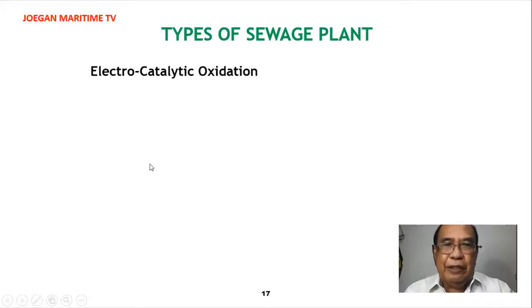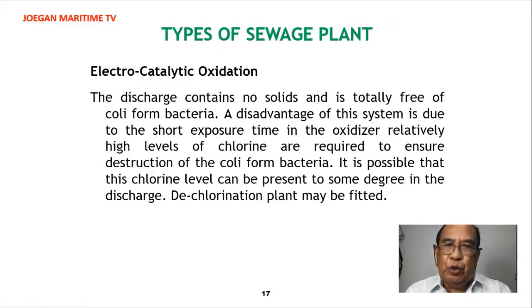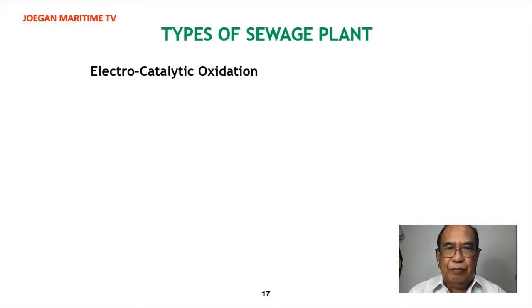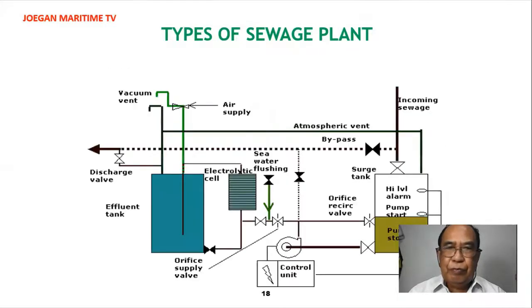With the electro-catalytic oxidation system, the discharge contains no solids and is totally free of coliform bacteria. A disadvantage of the system is that due to the short exposure time in the oxidizer, relatively high levels of chlorine are required to ensure destruction of coliform bacteria, and it is possible that this chlorine level can be present to some degree in the discharge. A de-chlorination plant may be fitted accordingly. These are examples of the electro-catalytic oxidation sewage plant.